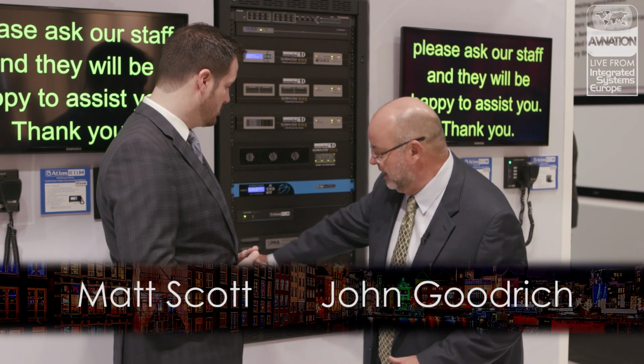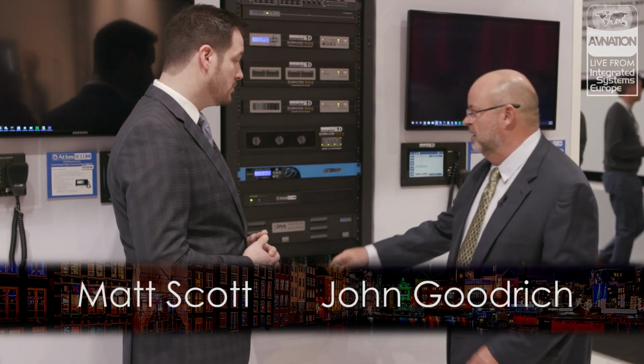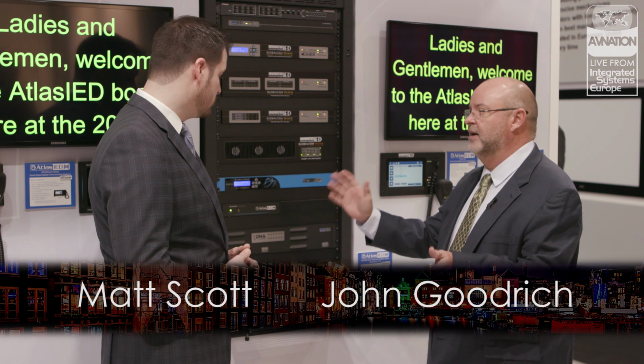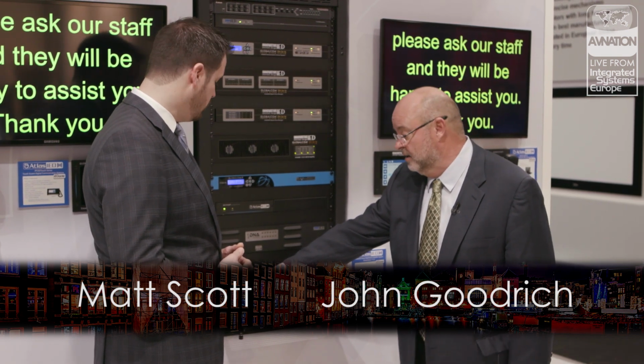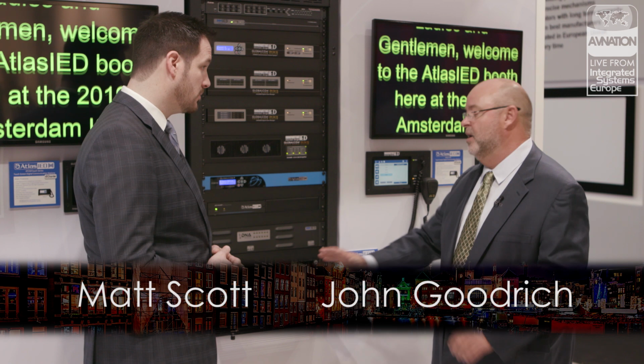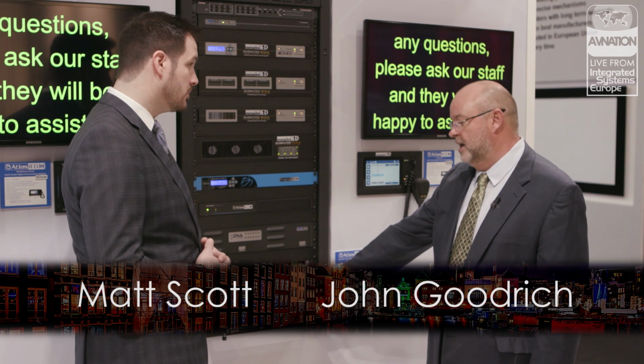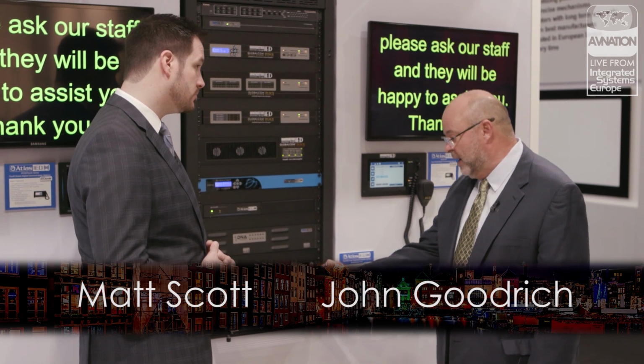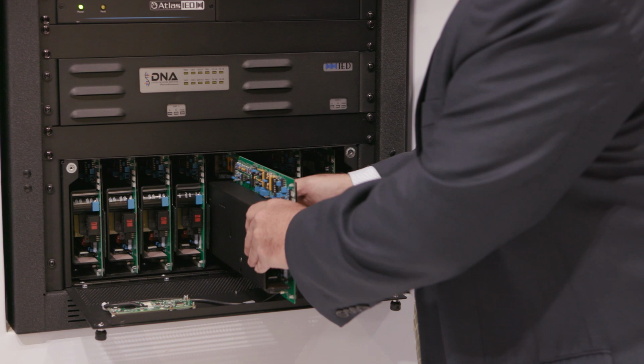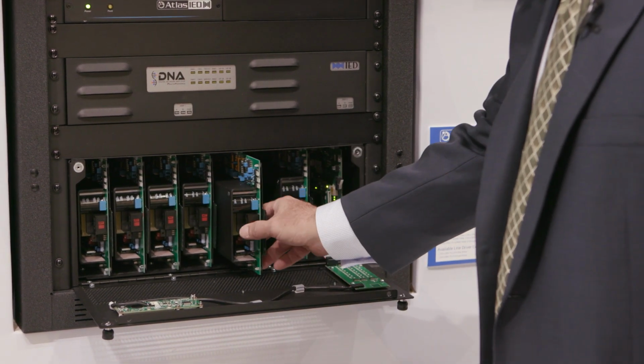So what does that mean? Out in the edge or the IDF closets, they'll have a switch and then basically one or two of the blue boxes, which are the main controllers, which are high availability and back each other up. Then we have the amplifier frame where each channel is 600 watts at 70 or 100 volts, 220 or 110, times 6, plus the backup amplifier, should one ever fail. Frankly they hardly ever do, but that's required for life safety, so the high availability is also built into the amplifier. It's right in there. And if you have to change an amp card, let's say it does fail, it's that simple. This card is a 1200 watt card, it weighs 2 pounds.